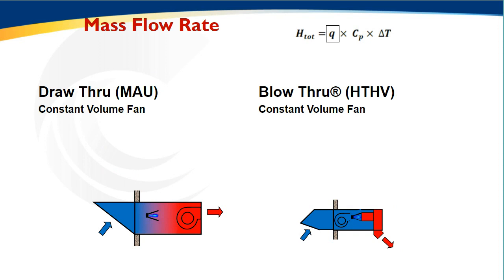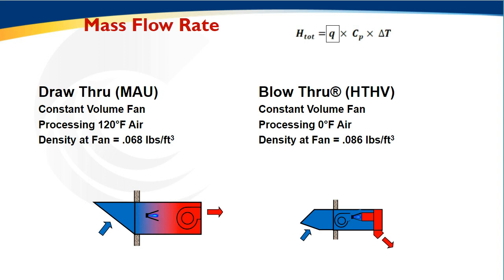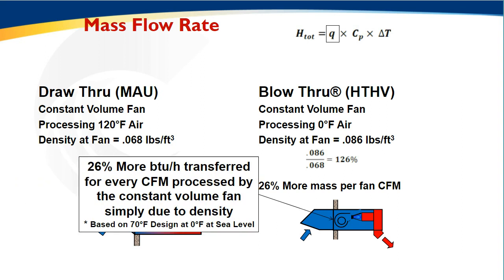And if I take our draw-through makeup air system and compare it to a blow-through HTHV system, the difference in density from 0 degrees to 120 degrees is about 26%. What does that mean from a convective heat transfer perspective? That means that by moving the blower to the cold airstream, HTHV systems can process 26% more mass per fan CFM. What that means from a convective heat transfer perspective is that I can deliver 26% more BTUs for every CFM processed. More heat, more energy, without more airflow.